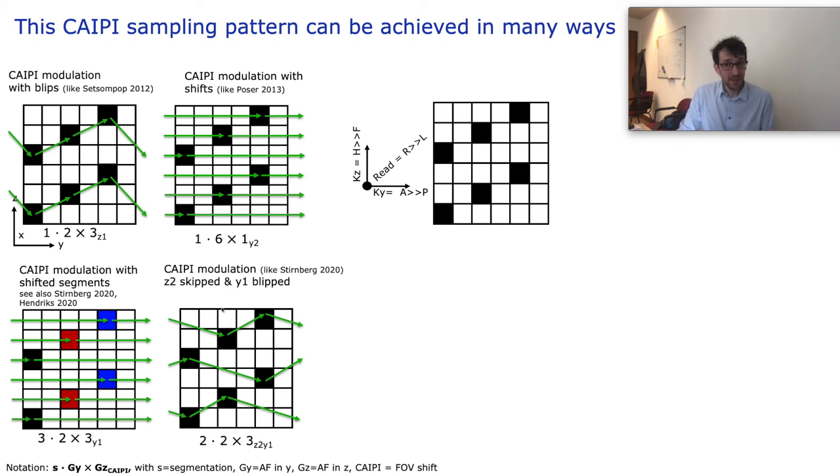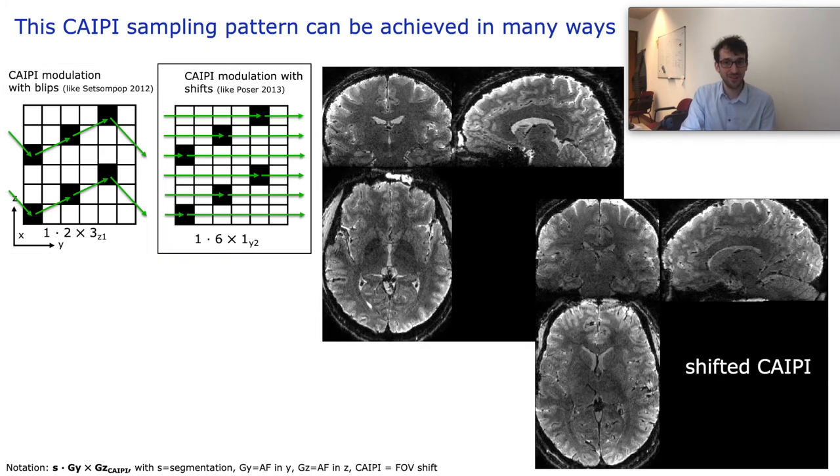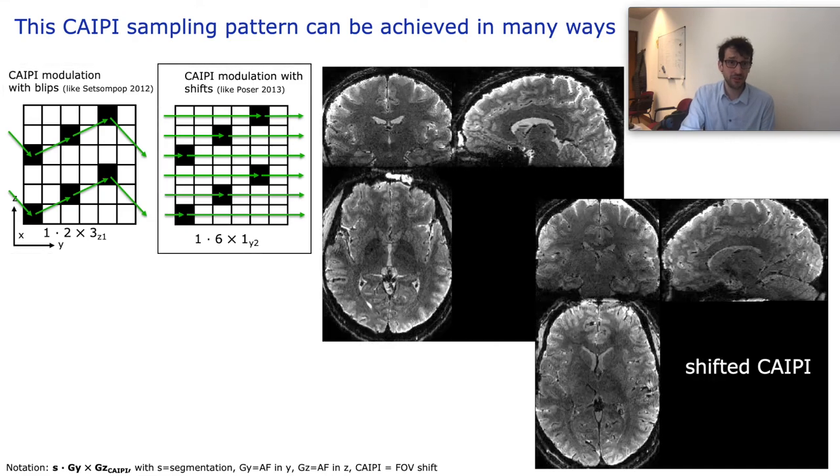To minimize the aforementioned artifacts, we followed the trajectory to keep the shot-to-shot variations orthogonal in a different dimension to the low bandwidth in Ky. Shown for two different participants, the very same CAIPI patterns result in very different data quality depending on whether or not the shot-to-shot B0 variations are mixed with the low bandwidth direction, tremendously increasing data quality with the same CAIPI undersampling pattern.